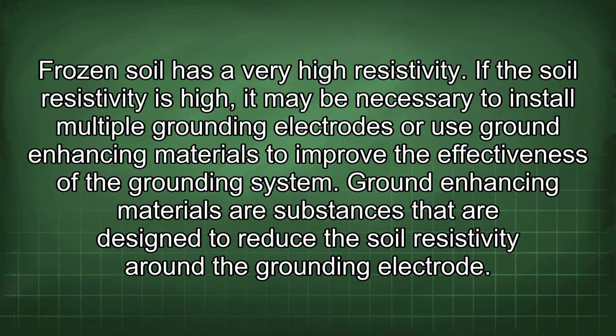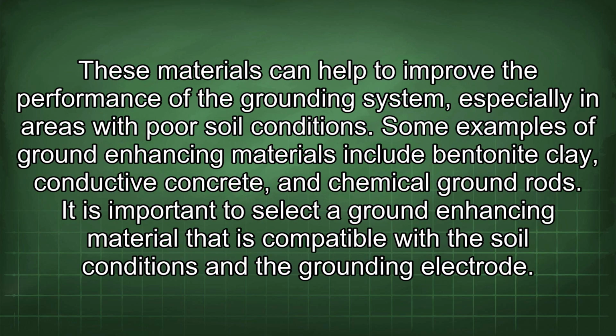If the soil resistivity is high, it may be necessary to install multiple grounding electrodes or use ground-enhancing materials to improve the effectiveness of the grounding system. Ground-enhancing materials are substances that are designed to reduce the soil resistivity around the grounding electrode. These materials can help to improve the performance of the grounding system, especially in areas with poor soil conditions. Some examples of ground-enhancing materials include bentonite clay, conductive concrete, and chemical ground rods.